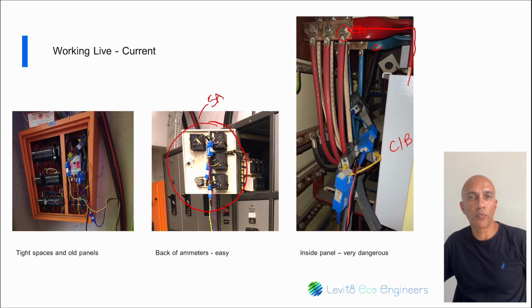The CT will also probably function like a transducer to get a small voltage or current into the instrument, but the conversion is all worked out in the software. So if you look at most instruments, perhaps your Fluke or Hioki instruments, they also operate like transducers. However, they're not 5 amp to 1 volt. They may be 500 amp to a certain voltage, but they operate in a similar fashion. But those CTs are specifically made for the instrument and you can't use them in any other instrument.